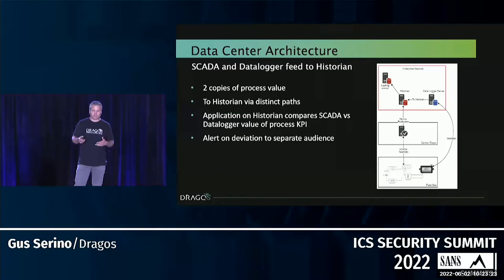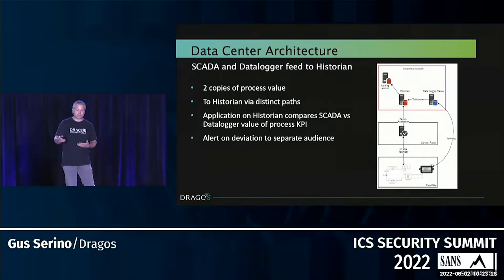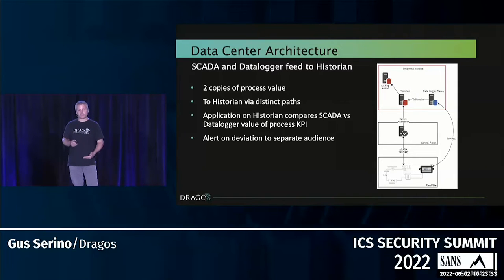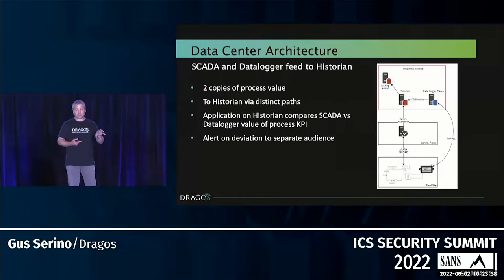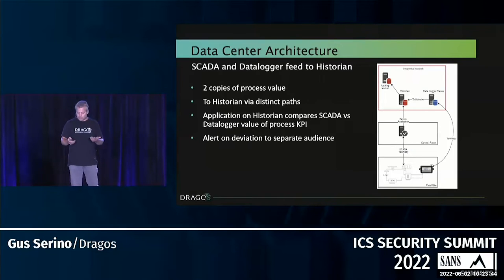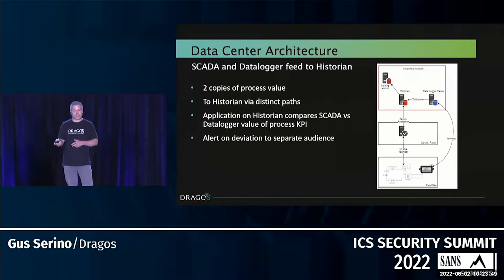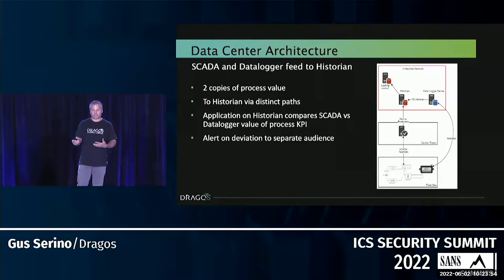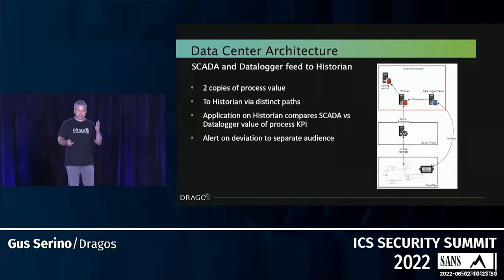In the data center architecture, you see the independent path to the data logger server on the enterprise network, alongside the normal SCADA telemetry path through the HMI. Both land in the historian, and a separate application sitting on top compares those two values and alerts if they're different. That's the crux of how we used what we already had — no new cybersecurity technology needed, just a way to validate those most important signals.